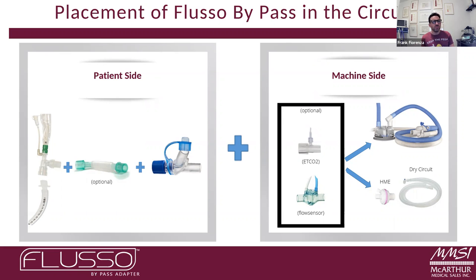I can do whatever I want on the machine side. I could rip the dry circuit off, go get my heated wire circuit, get the water, go get my nitric oxide - doesn't matter, whatever you want to do on that side you can do. Once you're done, you then just plug the ventilator back into the ventilator port, turn it on, and it'll go back to ventilating as usual.